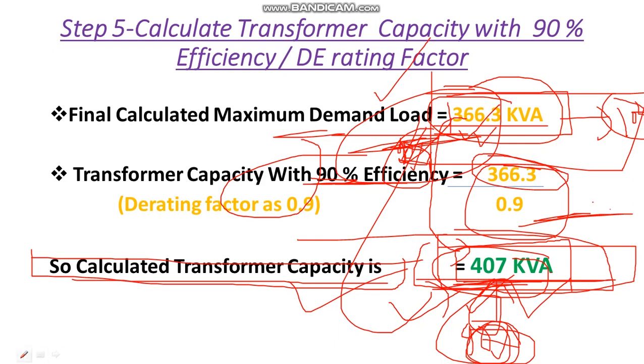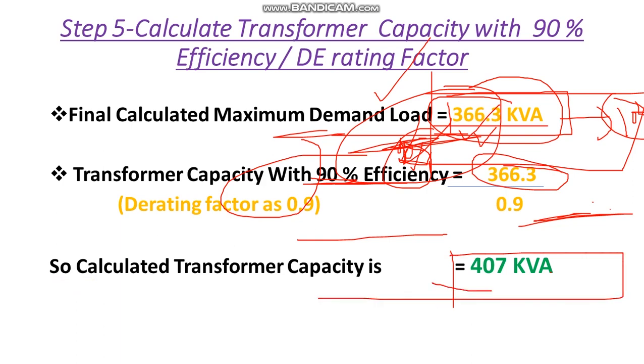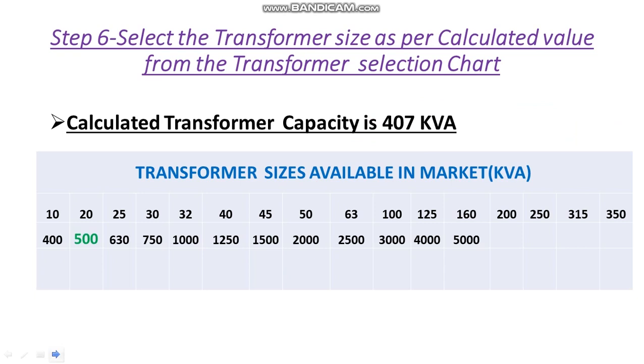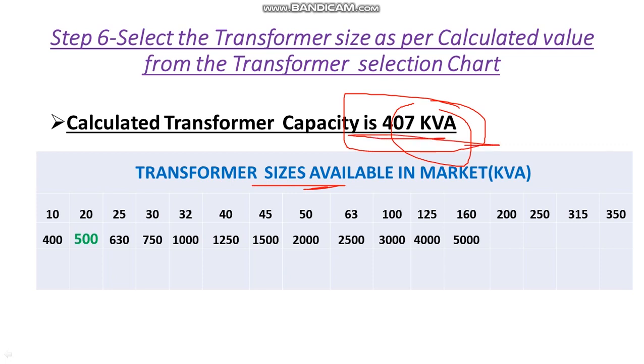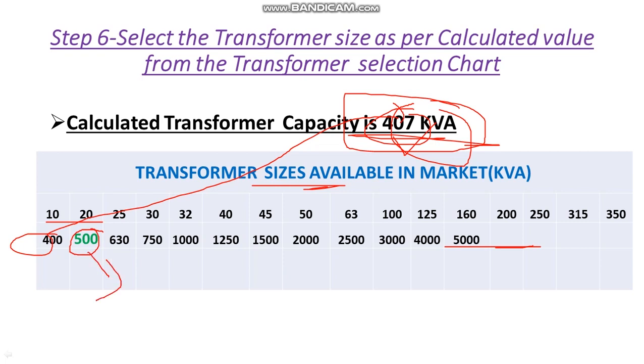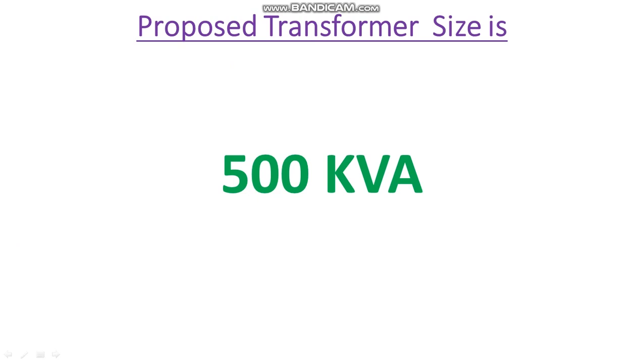We may not find the exact calculated transformer size of 407 kVA in the market, so we select from the transformer selection chart. The chart ranges from 10 kVA to 5000 kVA. Since 400 kVA is below our calculated value, we always select a size higher than the calculated value. The next available standard size is 500 kVA, so our final selected transformer size for this hotel building is 500 kVA.